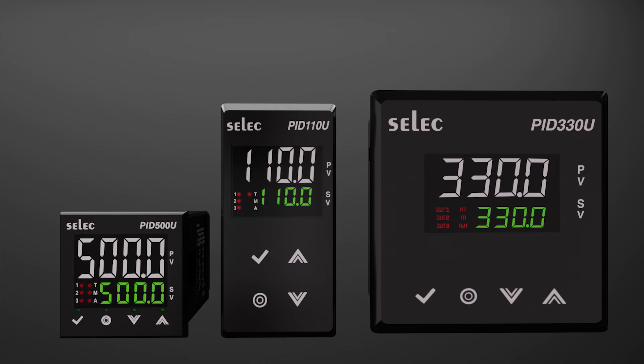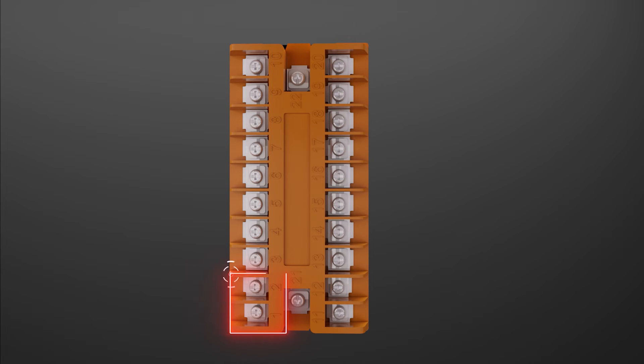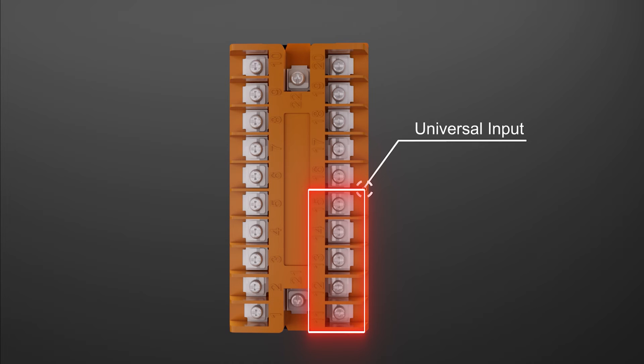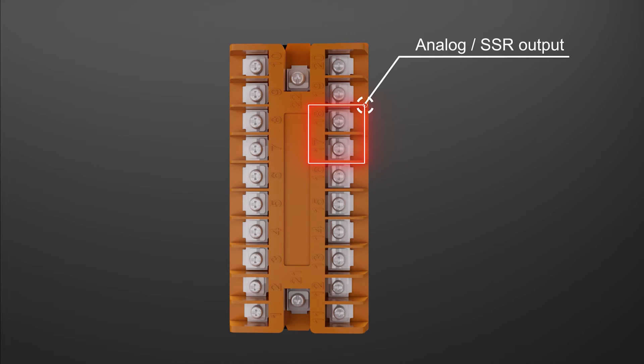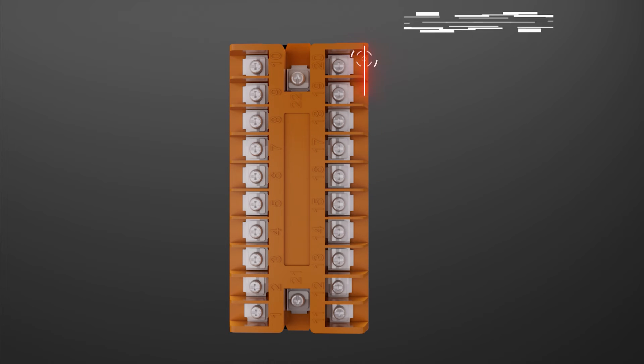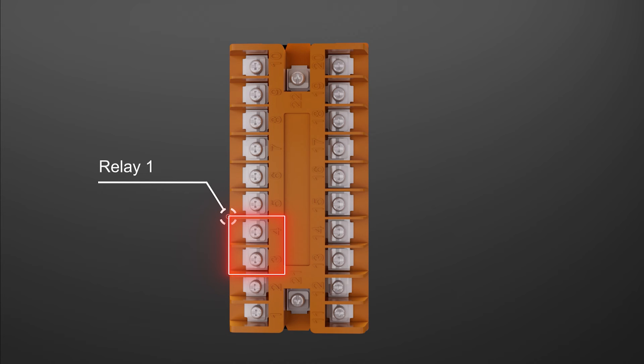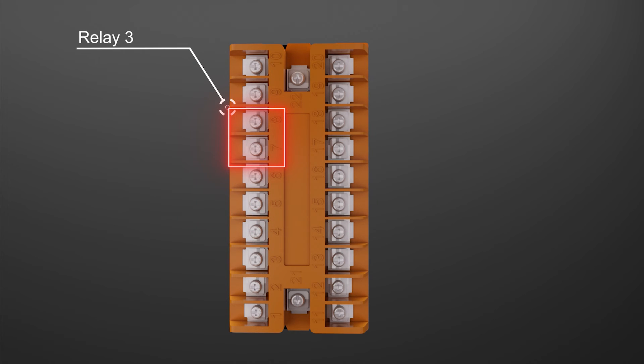These universal PID controllers are available in different sizes, making it feasible for the user to select according to panel cutout. For PID 110U: Terminals 1 and 2 for auxiliary supply. Terminals 11, 12, 13, 14, and 15 for universal input. Terminals 17 and 18 for analog current, voltage, or SSR output. Terminals 19 and 20 for RS-485 Modbus communication. Terminals 9 and 10 for inbuilt sensor supply — 24V DC. Terminals 3 and 4 for relay 1 output. Terminals 5 and 6 for relay 2 output. Terminals 7 and 8 for relay 3 output.